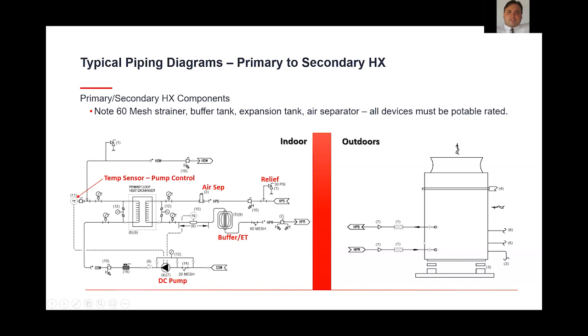We'll talk about some of that in a minute. So coming indoors, again, we're going to have that primary secondary heat exchanger. You'll need a means of pressure relief, an air separator, gauges, temperature and pressure gauges, a buffer and expansion tank. These could be a combined tank. Typically, they're broken apart into two separate items. You'll also have to include a fairly robust strainer, typically 60 mesh, to protect these heat exchangers in the water source module. And then you're going to have flush and fill valves.